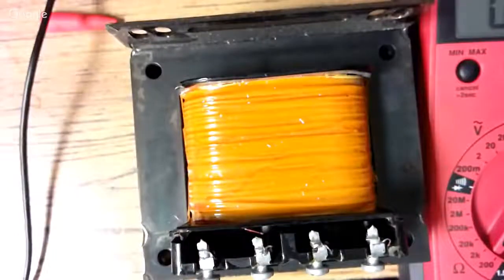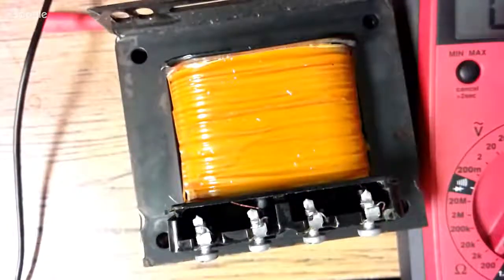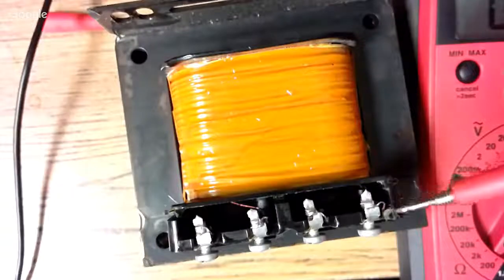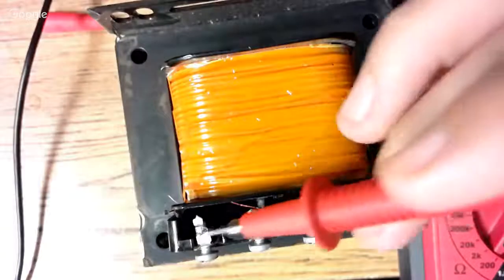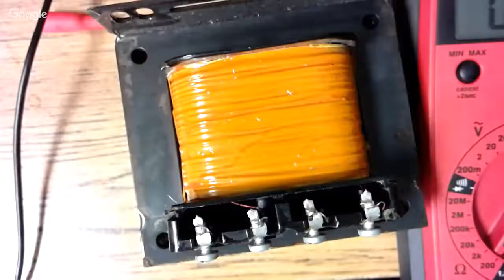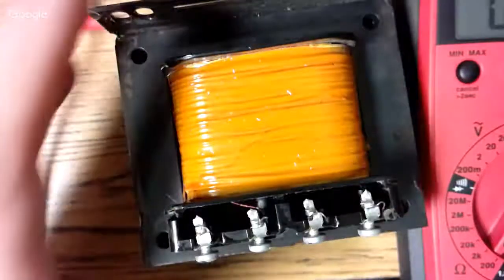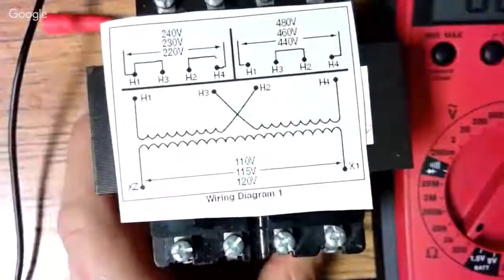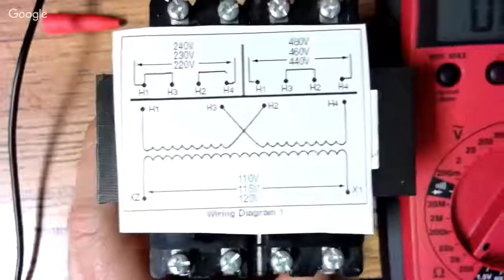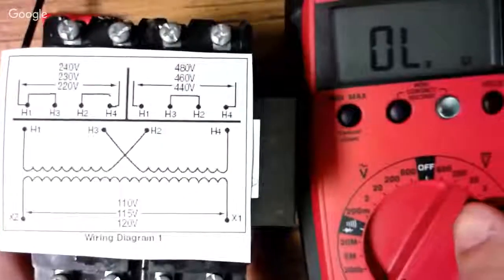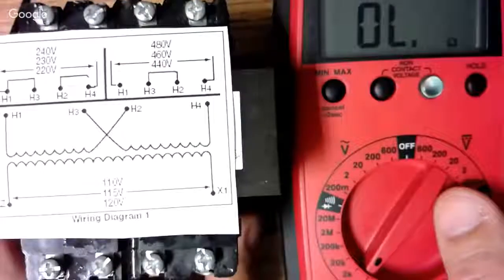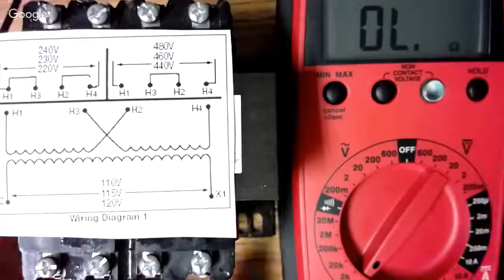If I look on the other side, which is our primary, and I look here, I can see a soldered wire here, here, here, and here inside this coil. So let's go back to testing. We're going to flip this back up. We'll put a little diagram on here. And probably more than likely, you set your meter to 200 ohms, which will be perfectly fine, which is what I've done. Let's see if we can get them both in there.